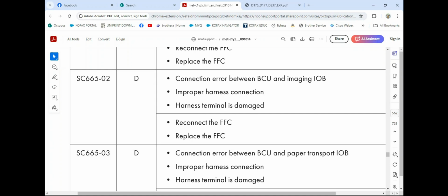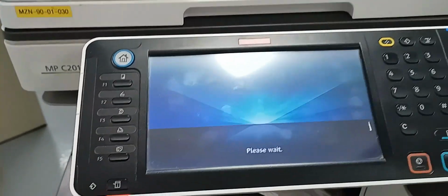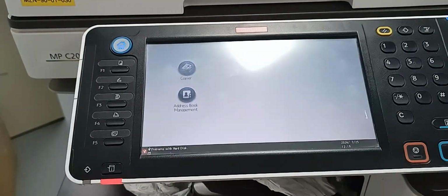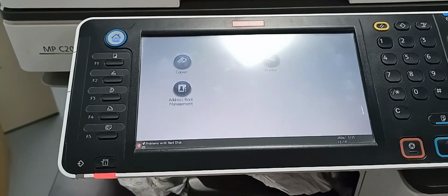Based from the service manual, the error description is connection error between BCU and imaging I/O board, improper harness connection, and harness terminal is damaged, and the solution is reconnect the FFC or replace the FFC. We restarted the machine to confirm the error code.